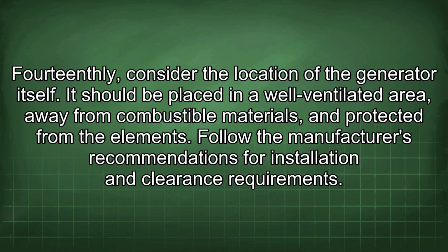14thly, consider the location of the generator itself. It should be placed in a well-ventilated area, away from combustible materials, and protected from the elements. Follow the manufacturer's recommendations for installation and clearance requirements.